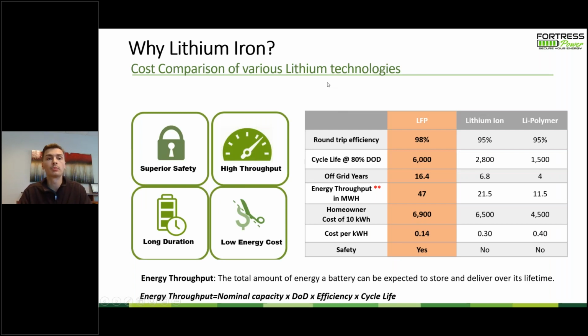So if we chalk up why lithium iron, looking at these different chemistries, I think the four things to keep in mind are the superior safety of LFP, very thermally stable, and very able to have high energy throughput and safety. Energy throughput is essentially the total amount of energy a battery can be expected to store and deliver over its lifetime. For example, energy throughput is 47 megawatt hours on LFP, while lithium ion or polymer can't even break 25 megawatt hours.